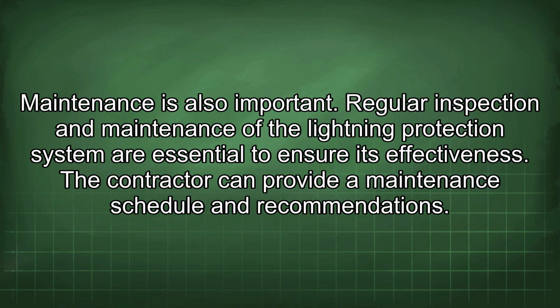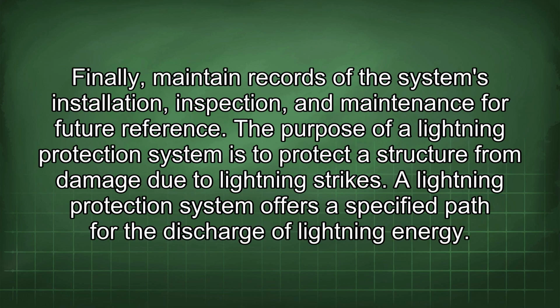Maintenance is also important. Regular inspection and maintenance of the lightning protection system are essential to ensure its effectiveness. The contractor can provide a maintenance schedule and recommendations. Finally, maintain records of the system's installation, inspection, and maintenance for future reference. The purpose of a lightning protection system is to protect a structure from damage due to lightning strikes. A lightning protection system offers the specified path for the discharge of lightning energy.